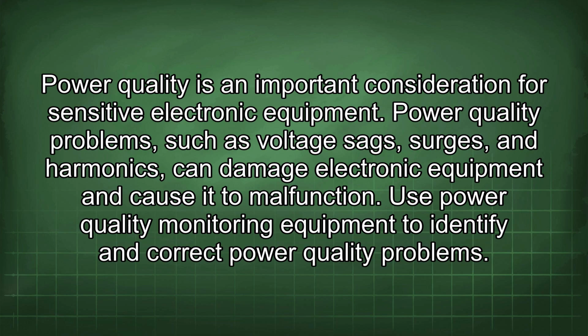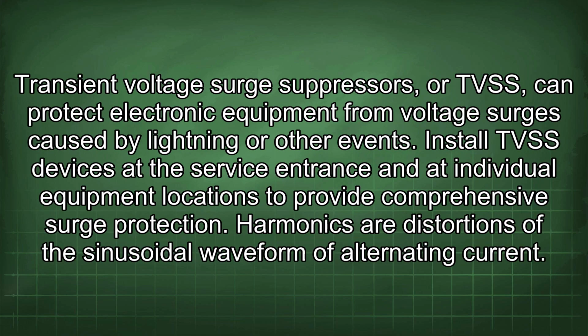Power quality is an important consideration for sensitive electronic equipment. Power quality problems such as voltage sags, surges, and harmonics can damage electronic equipment and cause it to malfunction. Use power quality monitoring equipment to identify and correct power quality problems. Transient voltage surge suppressors, or TVSS, can protect electronic equipment from voltage surges caused by lightning or other events. Install TVSS devices at the service entrance and at individual equipment locations to provide comprehensive surge protection.